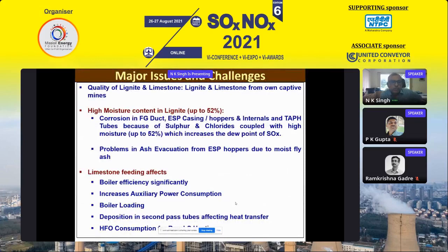Because of this lignite, there is a major issue of corrosion in the flue gas duct, ESP and casing hoppers, causing partial loading and causing problems in the performance of the ESP also. This is because moisture is there, sulfur is there, chloride is there, and this all forms acid. And because of high moisture, the dew point temperature is also increasing. So that is a major challenge for us. If anybody in the audience has some idea regarding this corrosion of the ESP casing, ducts and hopper, it would be helpful for us.